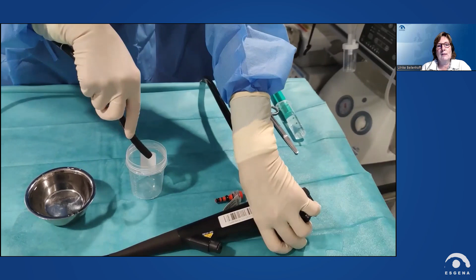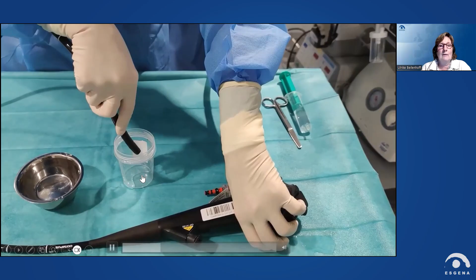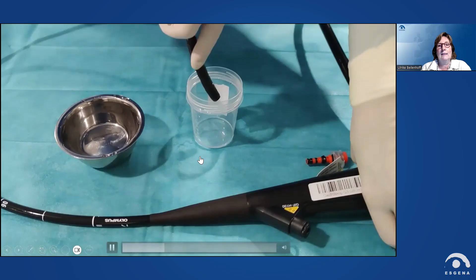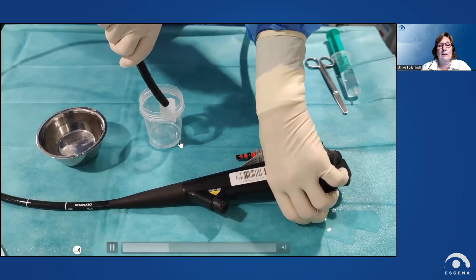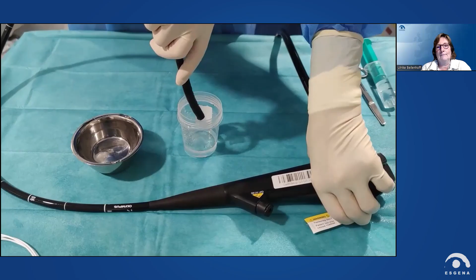So the first thing is you switch on the light source, you press the water valve and you rinse the water channel with that, and you collect the water, or the saline, here in this container. If you then want to rinse the air channel, you switch to the cleaning valve, and you press the valve and you rinse the air channel and also collect the liquid in that container. So that is the first step.